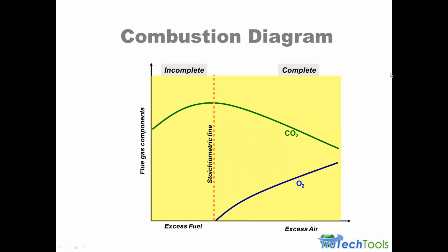This next line we'll lay down is the line for carbon dioxide, and we talked about that as peaking out, or having the most available at the stoichiometric line, or that perfect line of chemical balance. On this side, the air-to-fuel ratio isn't producing the maximum amount of carbon dioxide, and on the other side, the line drops off. This is kind of interesting. Why would this line drop off? What's happening over here to cause this drop-off? Well, these are all volume concentrations of the flue gas. So as we add more air and more oxygen, there's less concentration of CO2. And that's what your combustion analyzer is measuring, concentrations. It's not counting every molecule, but it's how much oxygen in this sample, and how much CO2 in this sample. As we add more air, hence more oxygen, the amount of CO2 is diluted and it goes down.